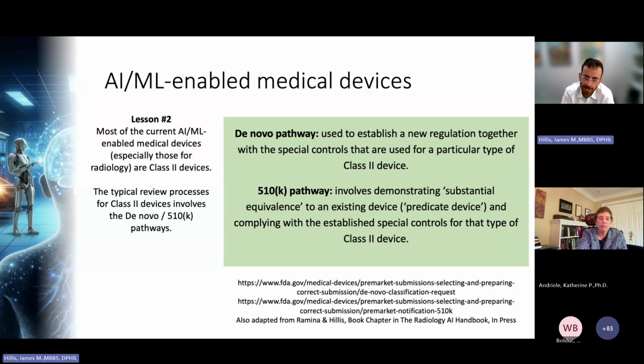I'll say they haven't necessarily all used Viz as the predicate device. Viz was the initial predicate that would have been used by the first device that came through on the 510K pathway, but it's possible to use one of the other devices that has come through as a 510K device as a predicate device. You don't need to use the de novo device. But essentially, Viz was the first of over 80 devices that have now come through as triage devices.